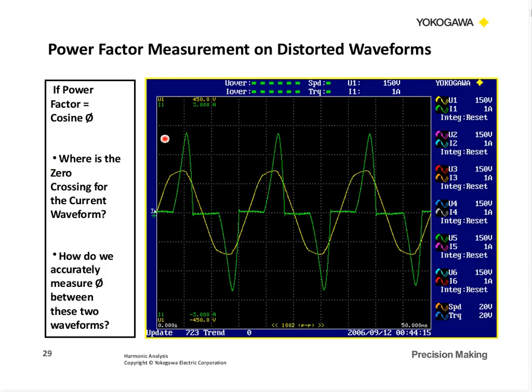Power factor measurement on a distorted waveform. I said earlier that we have to look at power factor, not cosine of theta. We're taught that a lot in school to begin with, and that's fine if you work at the power utility or with clean sine waves, but most of our work is not that type of work anymore, is it? So how do we accurately measure, if we were trying to do a phase angle on this, a time? We've got to pick some type of zero crossing. And so where's a common zero crossing? Well, you might say it could be at the peak, but it's very difficult to determine that exact peak. You might take, on this current, maybe halfway in between the rising and falling edge here, and then the difference between that and the voltage crossing. A lot of different ways. I don't think we would ever agree on where the true zero crossing might be. So it's very, very difficult to do.